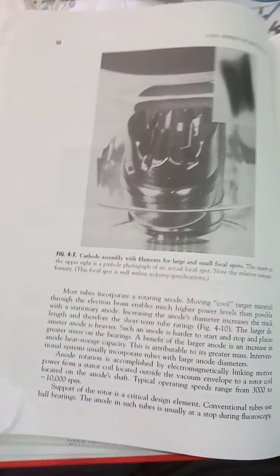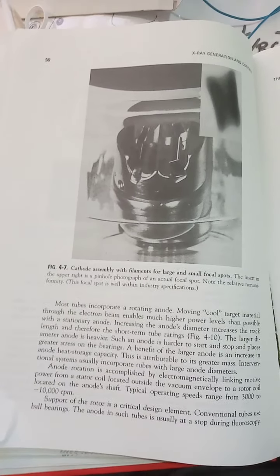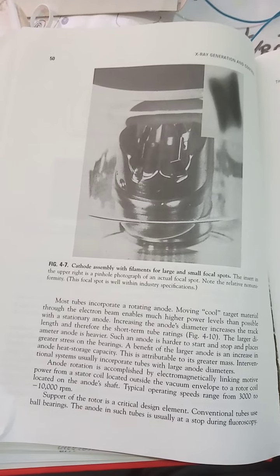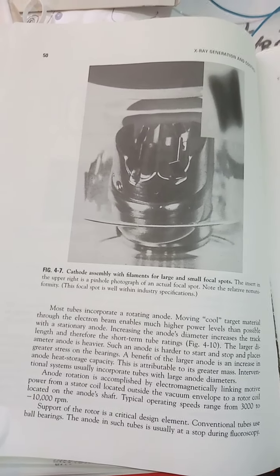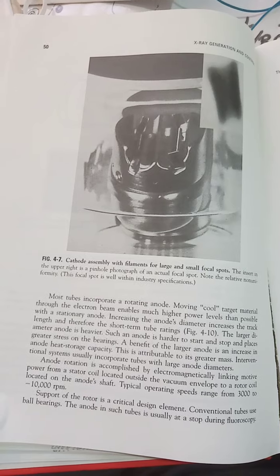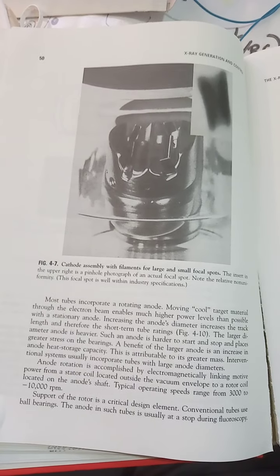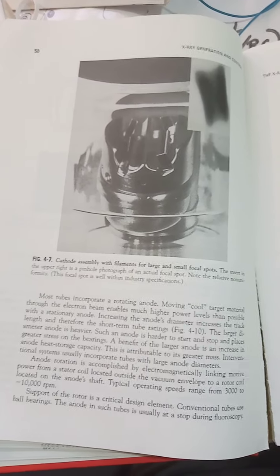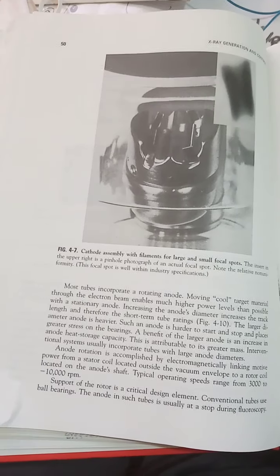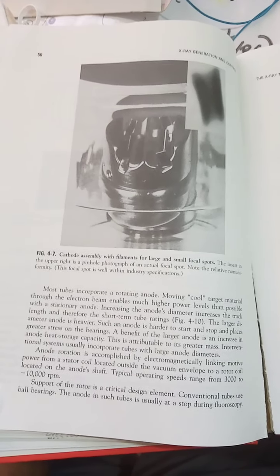This is image 4.7, the cathode assembly with filaments for large and small focal spots. The insert is the upright. In the upright is a pinhole photograph of an actual focal spot. So it's obviously a small component of the X-ray tube.